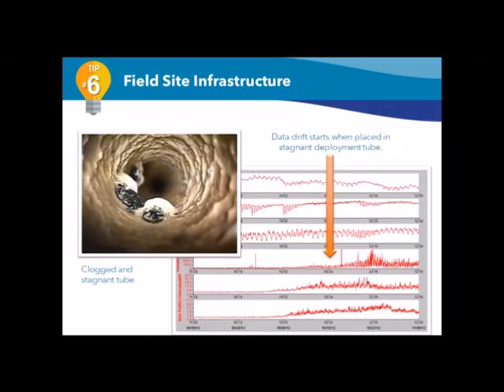I had a customer call in who was having problems with his dissolved oxygen probe. It calibrated fine, and it also passed his post-deployment calibration checks, no problem. The problem was when it was deployed and taking measurements—the dissolved oxygen readings would drop near zero in his pipe.